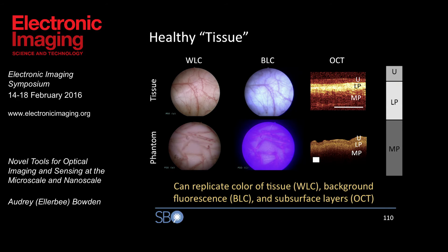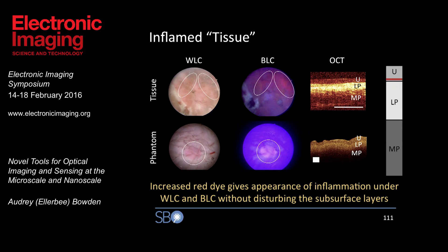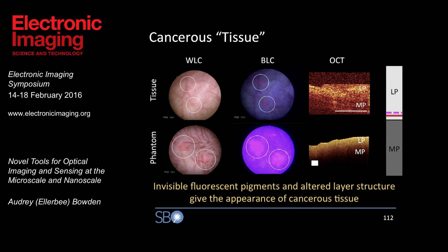Just a few pictures of the outcome. On top, you can see what healthy tissue looks like under the various modalities we cared about. On the bottom, you can see our phantom very well mimics many of the features of healthy tissue — the coloration, the appearance of vessels, and the slight illumination in blue light cystoscopy. In the case of inflamed tissue, we were able to mimic the slight redness under white light and slight fluorescence under blue light, but with maintained layer structure under OCT. In cancerous tissue, we can mimic various types of cancer — the appearance is much more red under white light, more concentrated fluorescence, and importantly, under OCT, the layers are removed. Developing this phantom was a really important tool to help characterize all the technologies leading us to use our probe for in vivo imaging of humans.